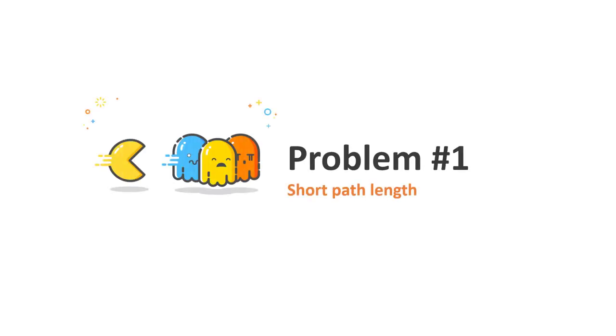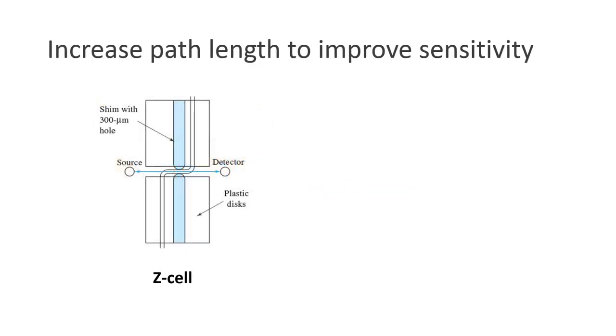So, the first problem we face here is a short path length. To improve the sensitivity of the detection, one common approach is to bend the end of the capillary into a Z shape to produce a path length as long as 10 times the capillary diameter.